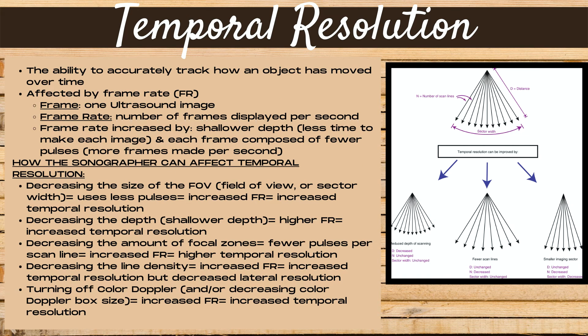Temporal resolution is the ability to accurately track how an object has moved over time, and it is affected by frame rate, or FR. A frame is one ultrasound image, and frame rate is the number of frames displayed per second. Frame rate is increased by shallower depth, meaning less time to make each image. Decreasing the size of the field of view, or FOV — also known as sector width — uses fewer pulses, which increases frame rate and results in increased temporal resolution.